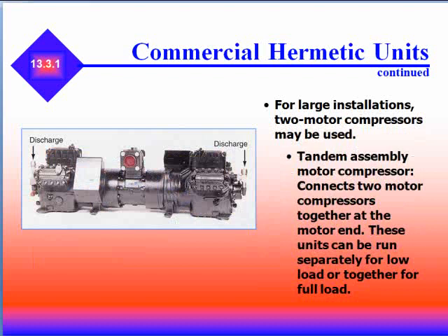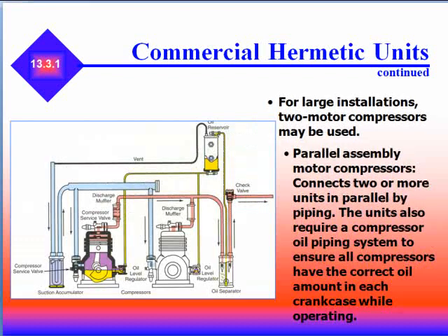For large installations, two motor compressors may be used. Tandem assembly motor compressors connect two motor compressors together at the motor end, and these units can be run separately for low load or run together for full load. Parallel assembly motor compressors connect two or more units in parallel by piping, and these units also require a compressor oil piping system to ensure all compressors have the correct oil level in each crankcase while operating.